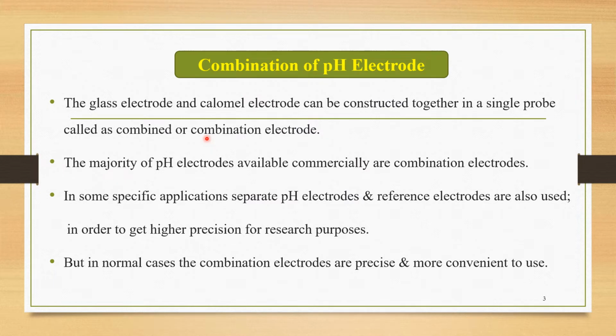So first of all, we are interested to know how these electrodes can be combined, that is called the combination of pH electrode. Now in order to determine or measure the pH of a particular solution, a certain assembly is required, and the electrode is one of the important parts as far as the measurement of pH is concerned. The glass electrode and calomel electrode can be constructed together in a single probe called a combined or combination electrode.